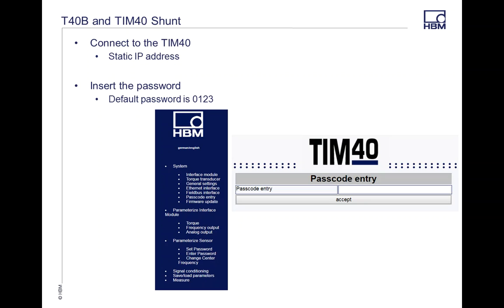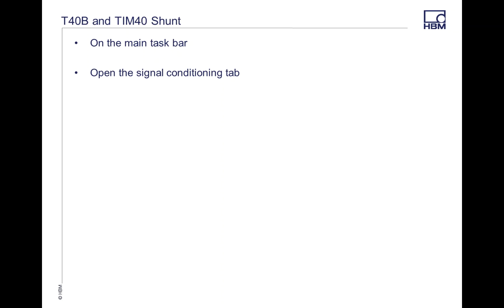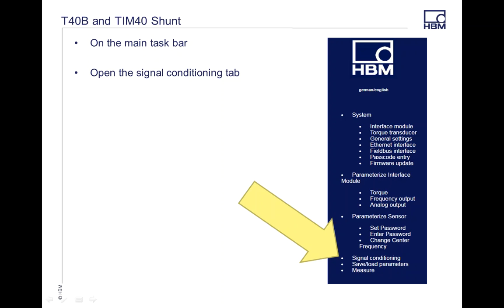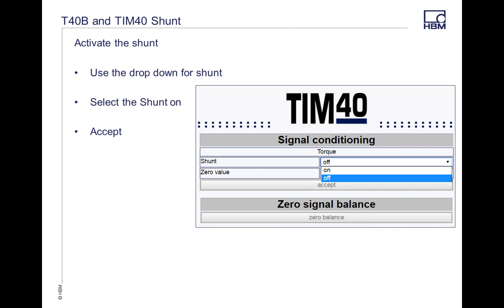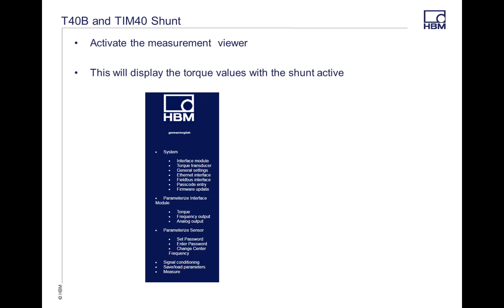Once you get into the TIM hardware, on the main taskbar at the very bottom, you're going to go to Signal Conditioning. This is going to be another one of the pull downs for the shunt active. So click that to on and then hit accept. On the TIM40 assistant, you cannot have more than one screen open at one time. So you have to bounce back and forth between the different screens and the T40B options.